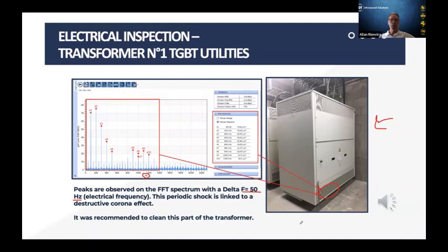So I don't know how well you could hear that, but I could hear it very well in my headset. We picked that up in a very noisy facility. So all of the background noise was filtered out by our SDT340, and all we heard was that destructive corona sound, and that's what you would expect to hear.